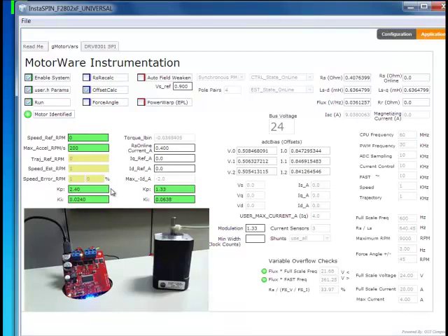This does not do any testing during motor identification to find out how to tune your speed controller, because to tune a speed controller, that's a mechanical system, and you need to know something about the inertia. So all we have is a good rule of thumb or a good guess that at least lets it be stable for initial operation. But you're going to want to tune this for your own applications. This can vary quite widely depending on the inertia and the size of the motor. For really high-speed, small motors, these speed control settings are usually much too stiff, and you're going to have to detune them. For this motor, it's actually pretty good.